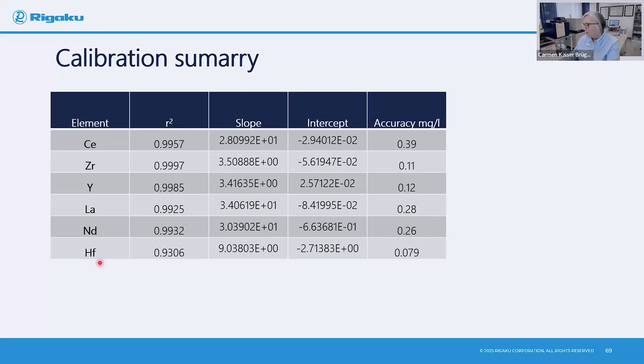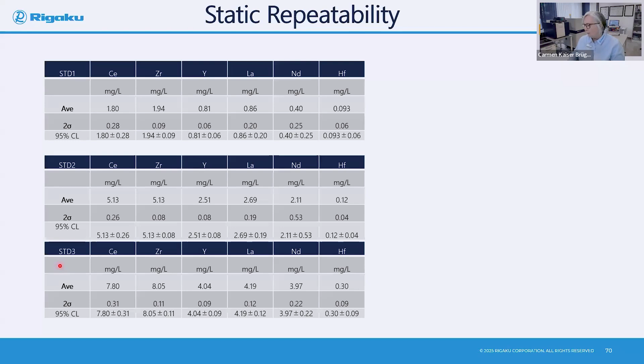What's also important in XRF is to establish what kind of repeatability we can achieve with the instrument. Using these calibration methods, we can do repeatability, and in particular static repeatability. Meaning we could prepare the sample several times, measure the sample several times, and see at the 95% confidence level what we can achieve for the elements that you see here. You can see that we can achieve very good static repeatability measurements at the 95% confidence level using this method.